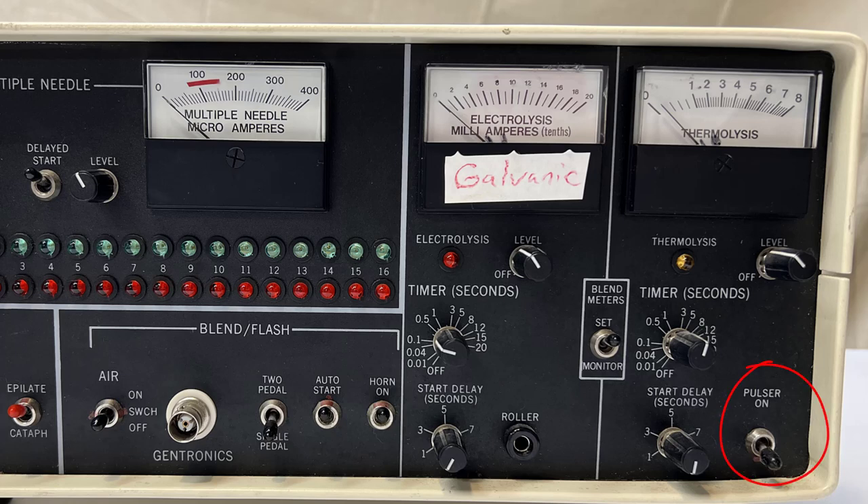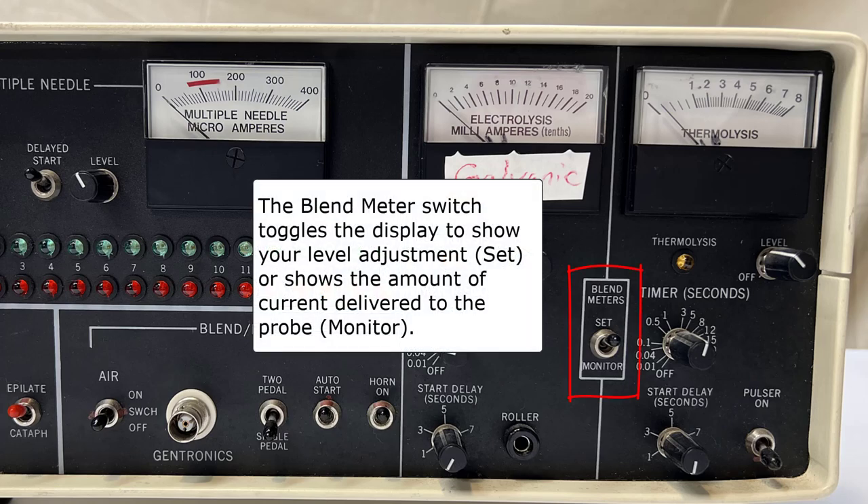When pulser is on, the energy pulses on and off instead of a steady, continuous flow of energy. Pulsing can cause discomfort in some clients. When toggled to set, the two meters are a visual indicator for the energy set by your level adjustments. When toggled to monitor, the two meters act as a visual indicator that shows the amount of energy delivered to the probe.